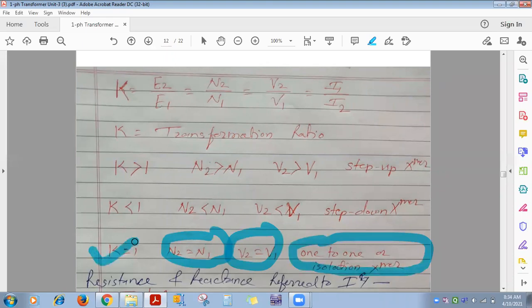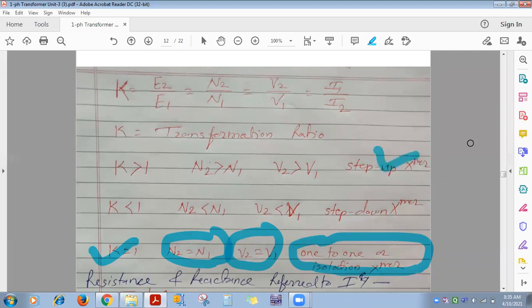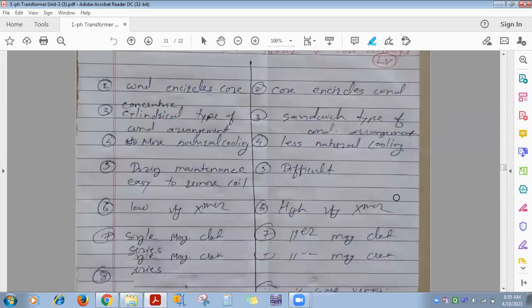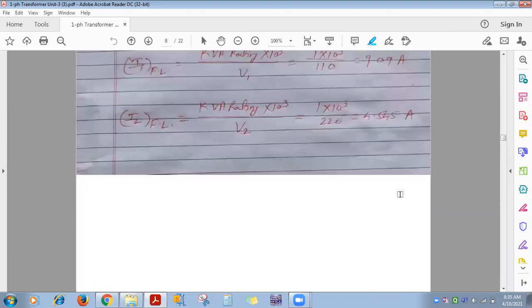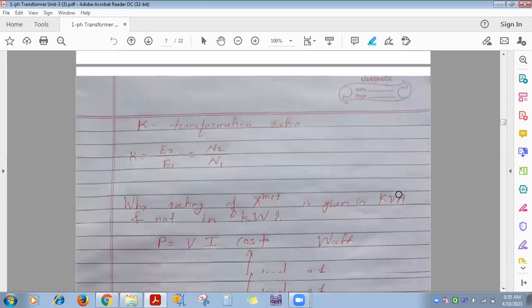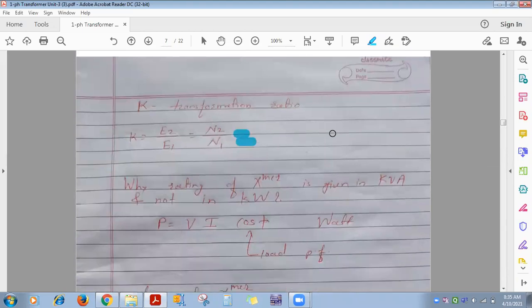Now, why is the rating of a transformer given in KVA and not in kilowatt? Input and output of transformer is AC. For single-phase AC: power = V·I·cosφ. For a motor, voltage range, current range, and power factor are all known once manufactured — so motor rating is given in watts, kilowatts, or HP. But for a transformer, the load on the secondary continuously changes (lamps, fans, heaters on and off), so cosφ continuously changes. However, voltage and current ratings are known. Since cosφ is unknown and variable, rating cannot be given in watts — it is given in volt-amperes (KVA).